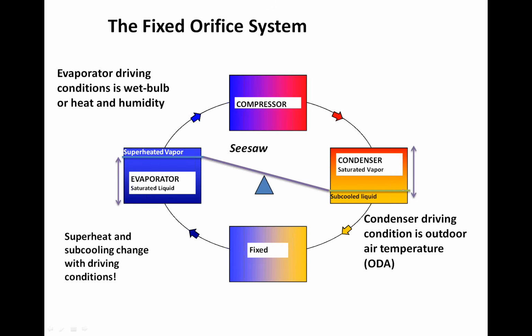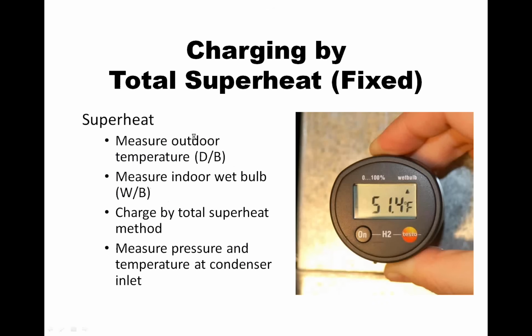All right. If we raise the pressure on that condenser, push down, think of it as a seesaw. It's going to lift up on the evaporator side. So as we push down here, that's going to mean a decrease in superheat. As we increase the pressure, we're forcing more refrigerant into the evaporator, and the superheat's going to go down. And if we go the other way, if we increase the pressure on the evaporator, it's going to drive the superheat up. And I'll show you this on the chart on the next page here.